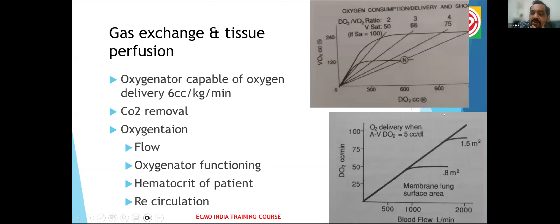So you need to maintain a saturation target. That's the reason why in a VV ECMO, the saturation target of around 75 to 80 came about. Coming to the downward graph here, as the blood flow increases, the delivery of oxygen increases proportionately. So you need to select an oxygenator membrane surface area of at least 1.5 meters square so that the delivery of oxygen will correspond to 6 cc per kg per minute.